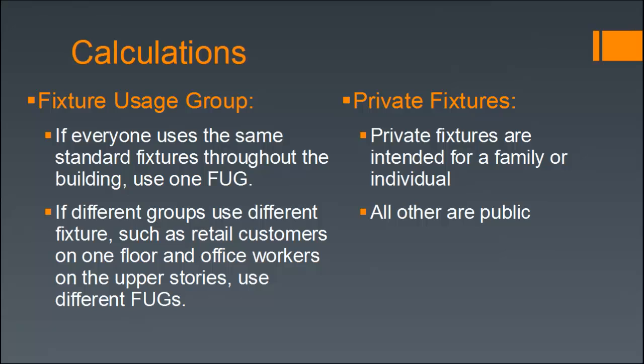So if everyone uses the same standard fixtures throughout the building, use one fixture usage group. And if different groups use different fixtures, such as retail customers on one floor and office workers on the upper stories, you need to use different fixture usage groups. Private fixtures that are only intended for individuals or a family are in a different category called private fixtures.